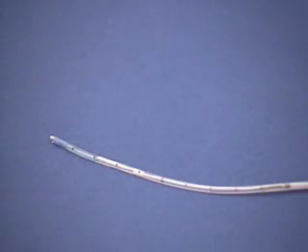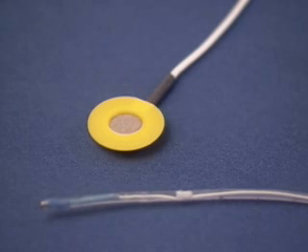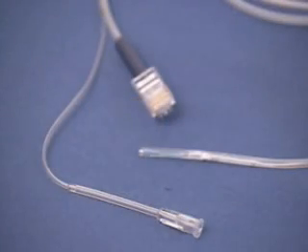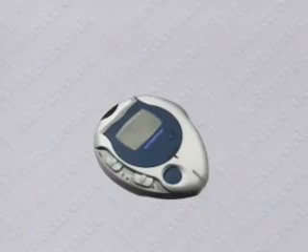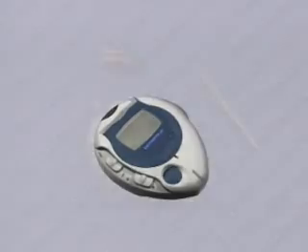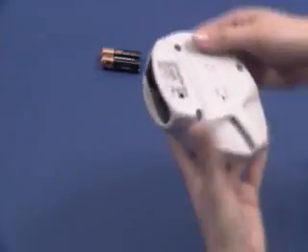Single-use catheters are available and provide significant convenience. Options include internal or external reference electrodes and infusion ports for manometric catheter placement. The Digitrapper is capable of recording up to 4 channels of pH and a single channel of pressure for manometric catheter placement.